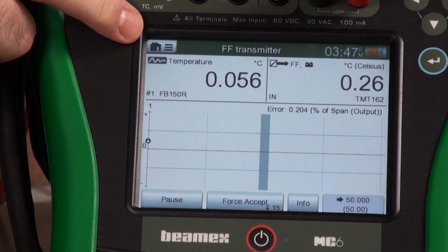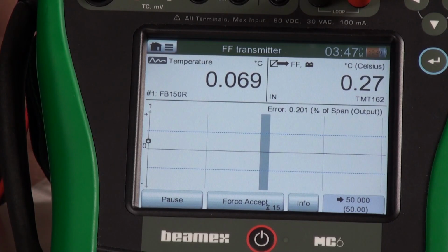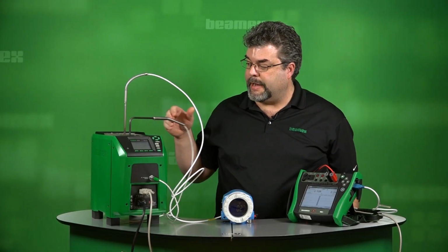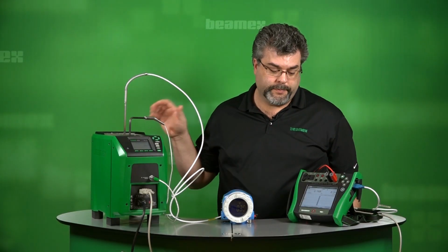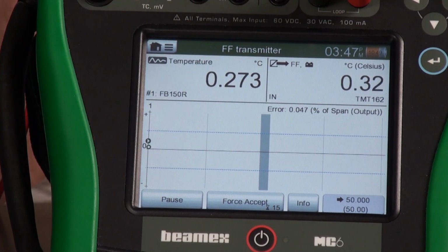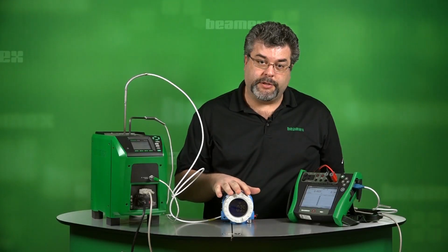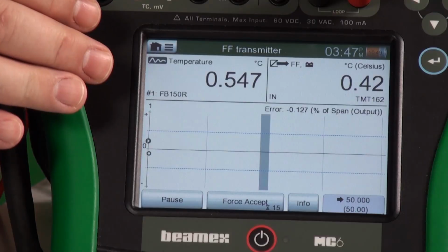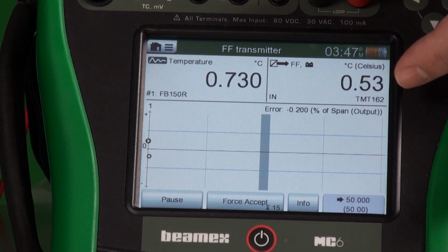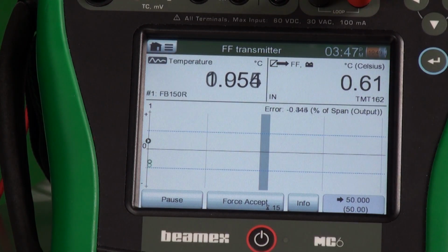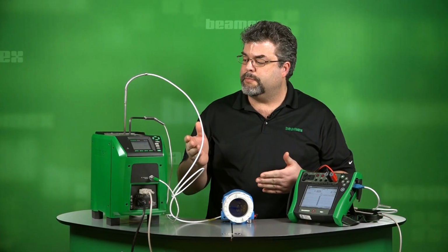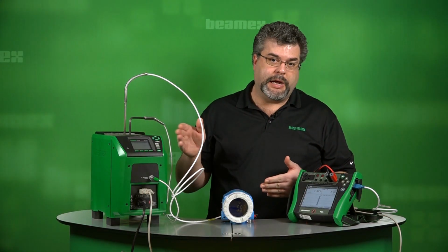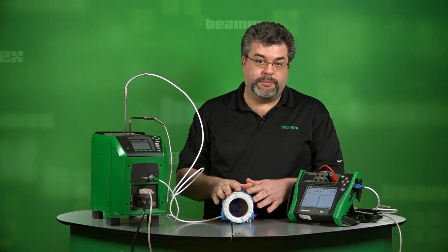On the upper left hand, we have our input. This is the actual value coming from our highly accurate reference probe right here. The output happens to be the output of the Fieldbus transmitter. We have a live reading of the error right above the graph on the right-hand side. It gives you a live reading, and there tends to be some lag between the temperature element and then the output of the transmitter.